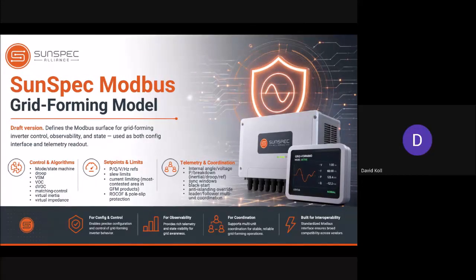So if you draw that imaginary line that's coming down, everything right now is defined where the flow comes down from the utility, goes across that line into a following mode only. Everything is defined with anti-islanding, anti-everything, right? Just disconnect, run away. Now that we have the hybrid machines, we've got rotating machinery, generators, etc., that can in fact support the utility, but there's no communication protocol on how to communicate that back and forth, how to communicate what state the machine is in, or how any of the controls work. This model is being looked at as, is it possible to add it in?